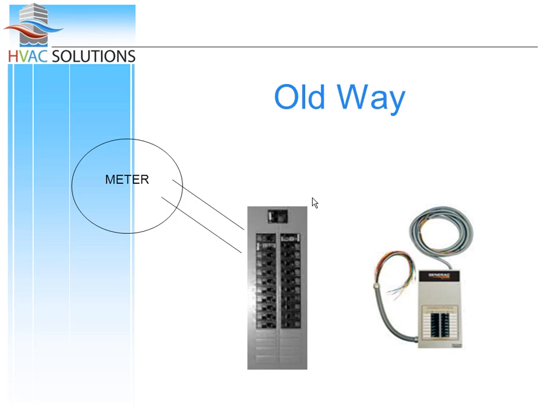If I go back, what is easy about doing it the old way? Well, the first thing is that you've got pre-wired whips. You've got a whip that goes out to the generator, and you've got a whip that goes to the circuit breaker panel. And secondly, where do you turn off power here? Well, it's pretty simple. You flip a switch in the customer circuit breaker box. It cuts off power, and then you can do your work.